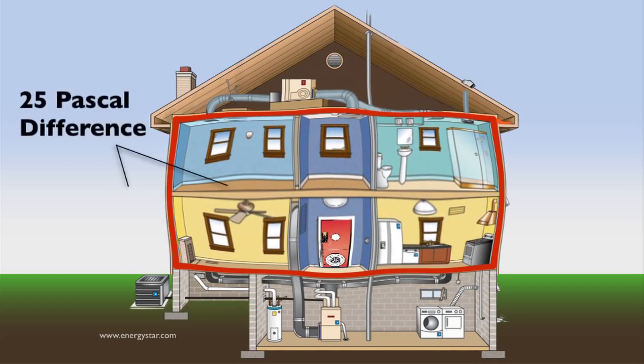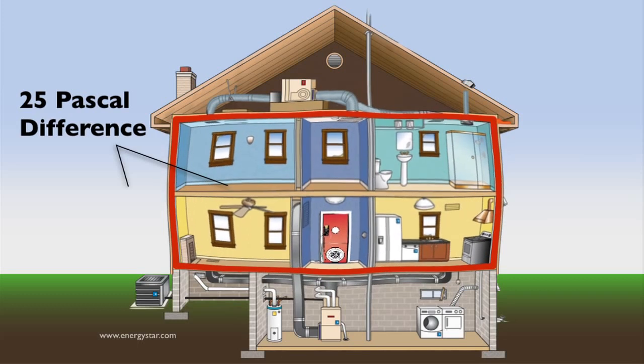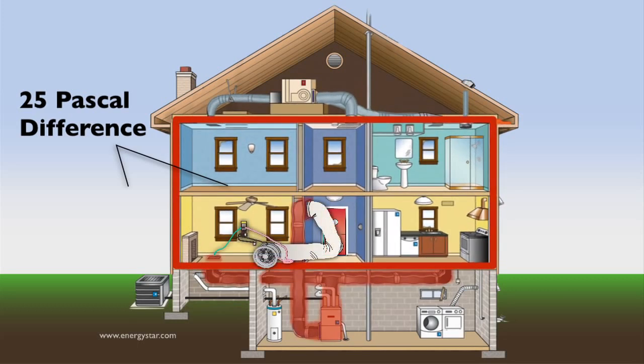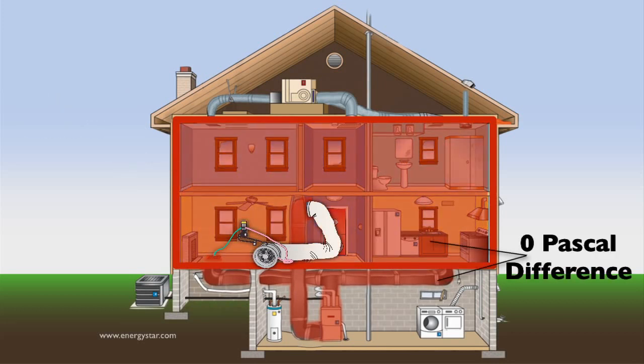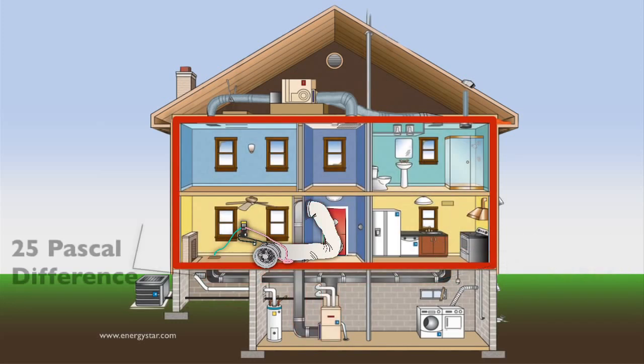With the blower door pressurizing the house to 25 pascals, turn on the duct blaster to pressurize the ductwork until the pressure difference between the ducts and the home reads 0 pascals. Because the blower door is pressurizing the house to 25 pascals, and the pressure difference between the ducts and the house is 0, the ducts are effectively the same pressure of 25 pascals. The resulting CFM 25 found on the right-hand side of the gauge represents the leakage to the outside of the envelope. This value will be used to calculate the percent duct leakage.